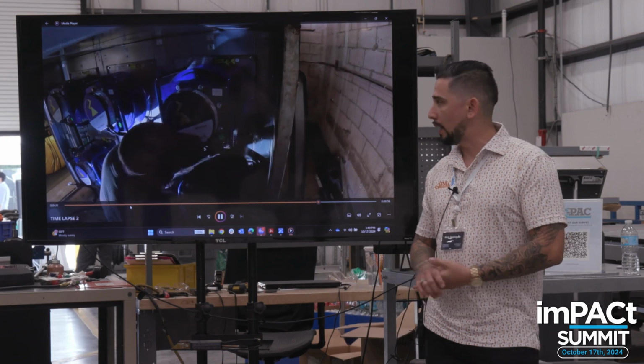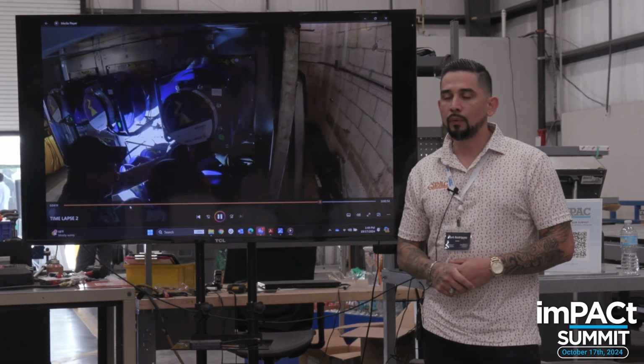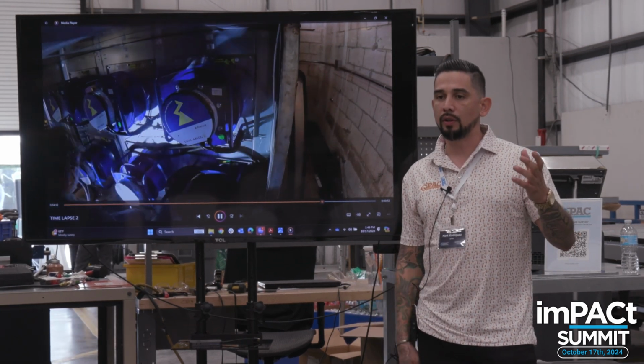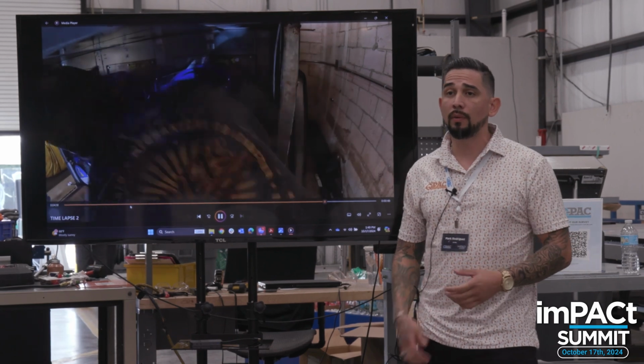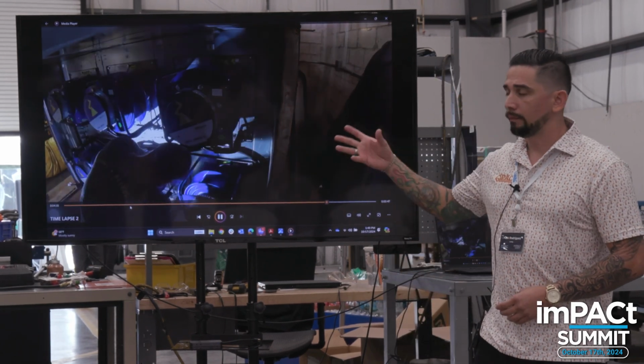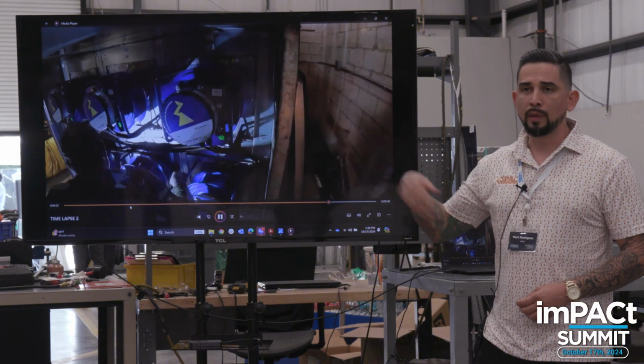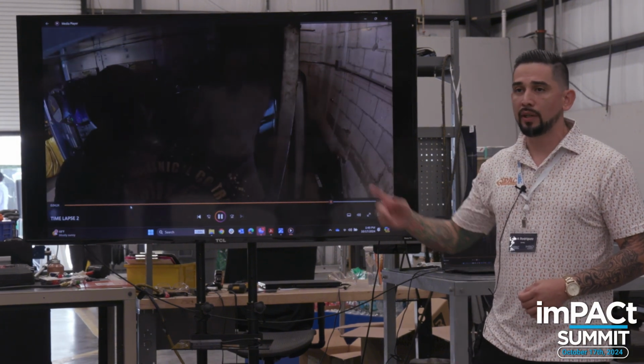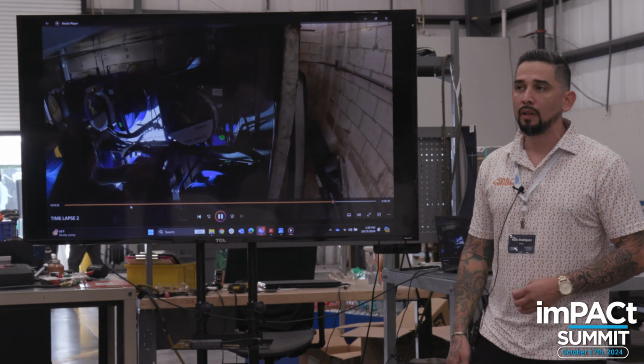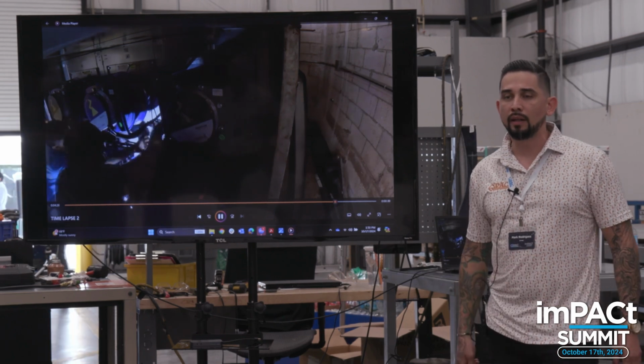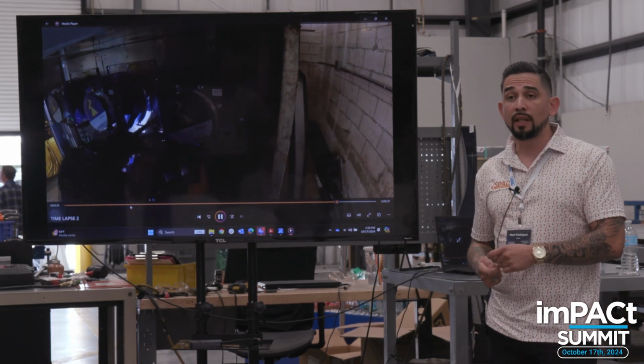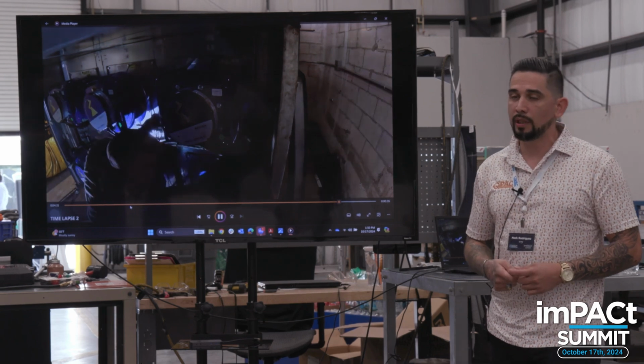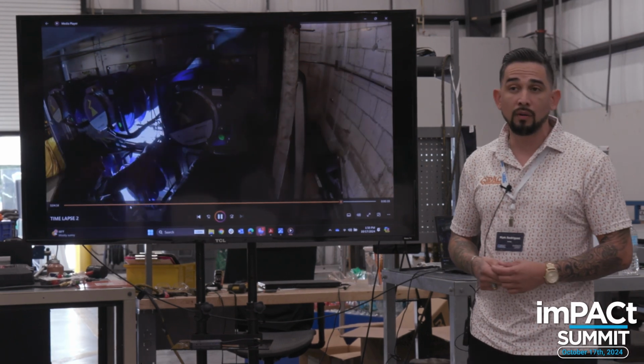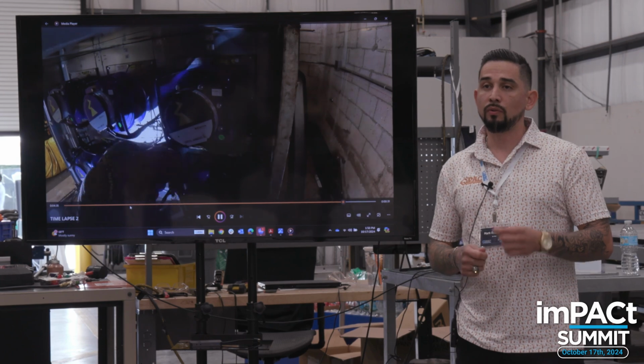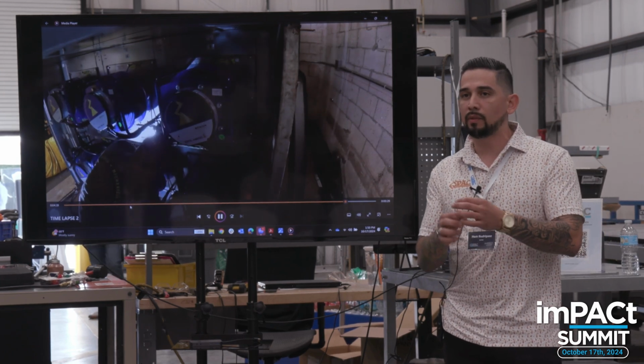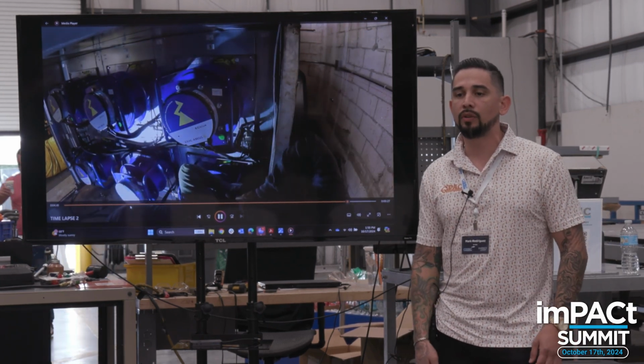Startup procedure, like I said, everything's in the manual. We have a startup procedure so you can check to make sure the cones aren't rubbing on the impeller. You want to spin them by hand first and make sure you don't hear any scraping or rubbing. Make sure all your connections are right - don't force a connection. Connections go in usually pretty smoothly. If you're forcing a connection, it's probably going in the wrong way, so you want to make sure it goes in nice and smooth and clicks like it's supposed to.